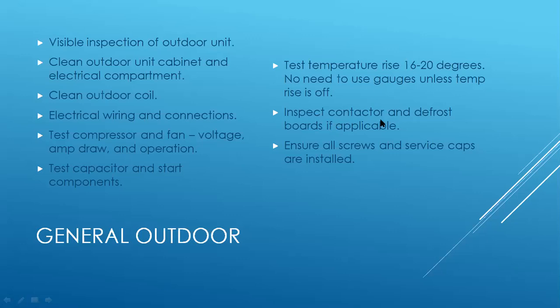Inspect the contactor, look for any kind of burnt marks, loose plates. Also, if you have any defrost boards, check those over, check your wiring. And this is a big one, ensure all screws and service caps are installed. If you leave service caps off, and if you get a leak or anything happens, well, they left the caps off. I don't know how many times I've heard that through the years. Or they didn't put all the screws back in. They didn't put the caps back on. That's just poor service, and it's an open invitation for free repairs down the road.